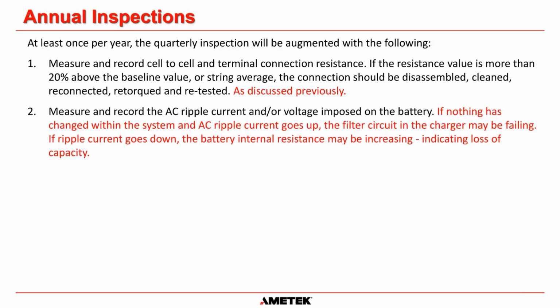And then for annual inspections, you augment the monthly and the quarterly, and then measure and record cell-to-cell and terminal connection resistance. And then it says here, if the resistance value is more than 20% above the baseline value or the string average, the connection should be disassembled, cleaned, reconnected, retorqued, and retested. As we discussed previously, that's the intercell connection.